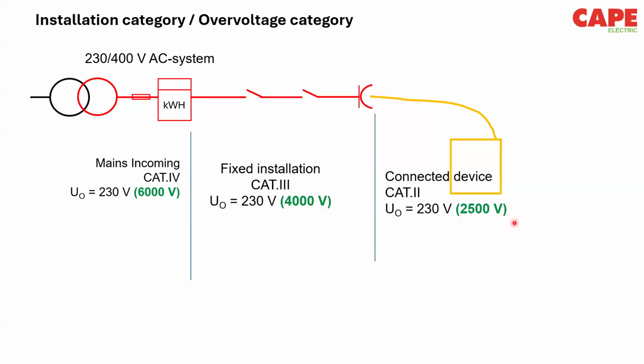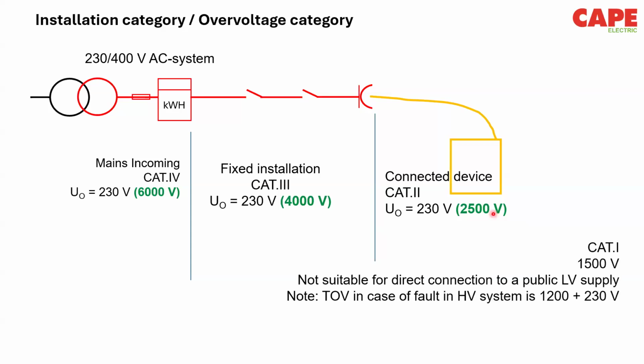Connected device in the sense any device which is directly plugged into your wiring system. Maybe, sorry, a TV, your machines, any machines which are directly plugged to your system. It is tested for 2.5 kV. And then we have a third category, category 1, which is not directly connected to the low voltage supply, and it is tested for 1.5 kV. So we are providing SPD so that this category is achieved and SPD is within this 2.5 kV or maybe even 4 kV impulse voltage.